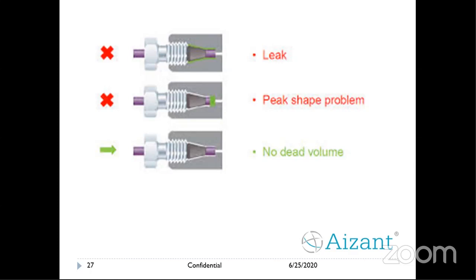If a small leak is happening, you will find a distortion in your peak shapes, or the resolution is lost, or a wavy baseline is coming, or there is a drift. You will find variation from injection to injection.